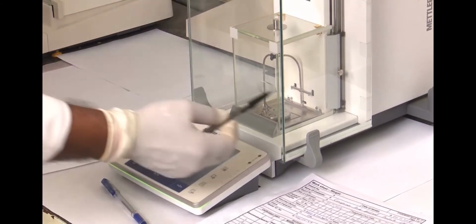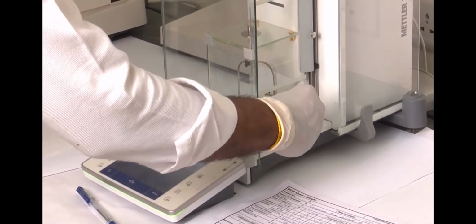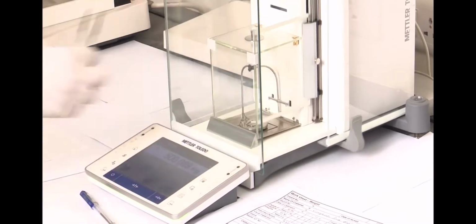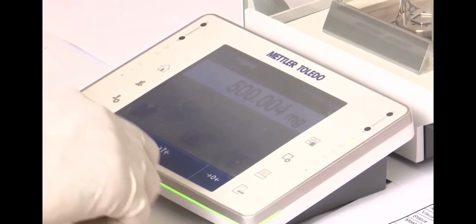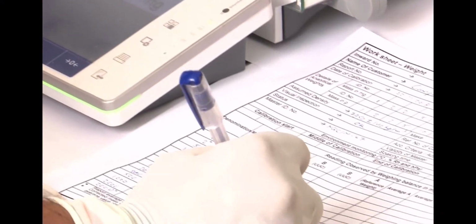Put again reference standard weight on the center of pan of the balance. Close the door, allow it to stabilize and note down the reading shown by weighing balance as A. In this way, one cycle is completed. Similarly, we can complete 2 more cycles.